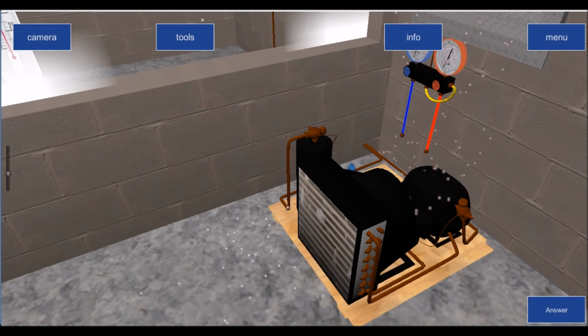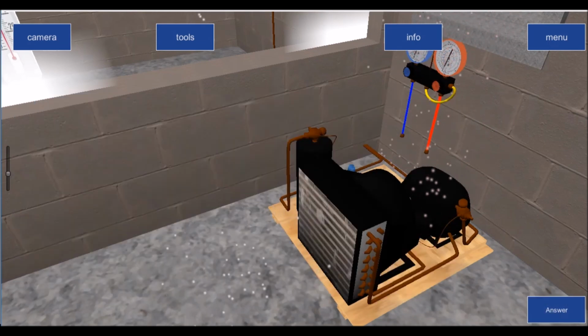So you're well spotted. Because basically the chart, what we're trying to do is we're trying to say, right, that lack of condenser capacity is down to higher than normal back pressure, higher than normal. It's actually normal to higher than normal head pressure. So in this particular case, we should have said the head pressure was okay. But 18 degrees would mean that the head pressure was too low. So this is when we got our lack of condenser capacity. So hang on a second now. That was fault 1 or fault 2? I think it was the second one.